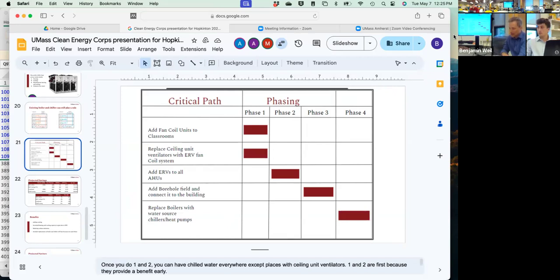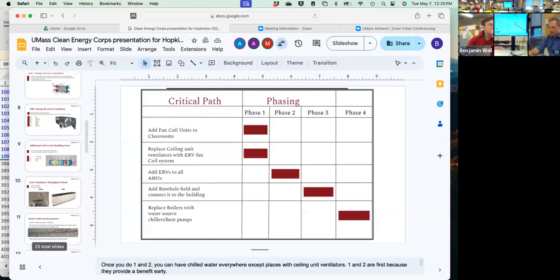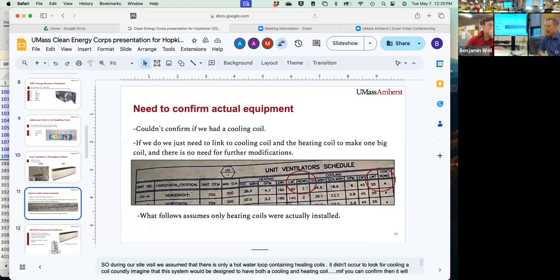Yeah, I would say, there are lots of different ways to fund things. In terms of capital, I would first, I hate to say it, assign Tim the job of investigating whether the unit ventilators actually have 4-row cooling coils just sitting there. If that's the case, why would you have a 2-pipe heating loop, but add a cooling coil for no reason? But if it's there, just like according to the schedule, then we're talking about a simple linking valve that turns the one heating coil and the cooling coil into one really big coil.